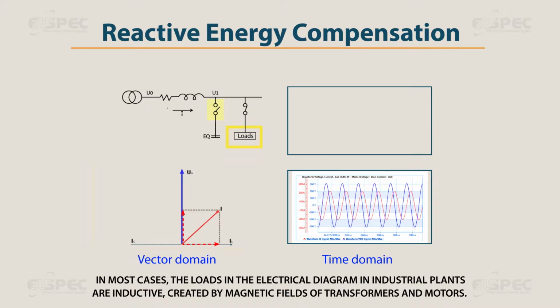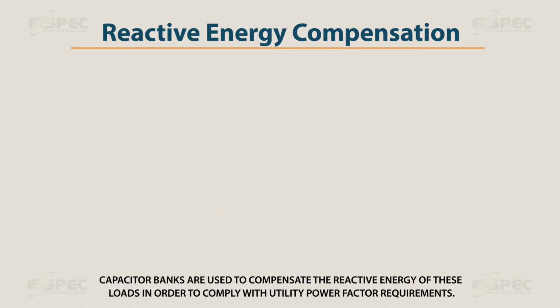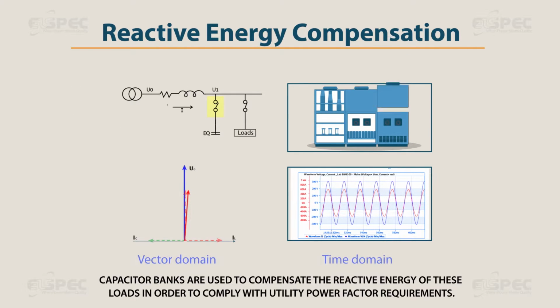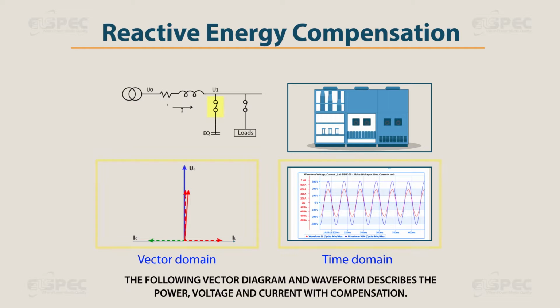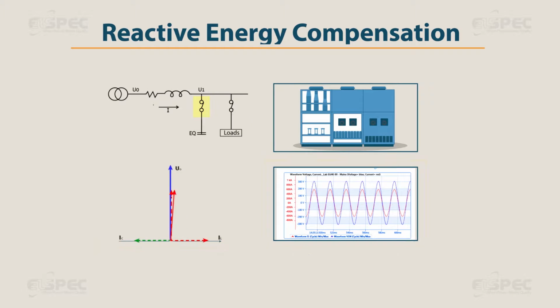In most cases, the loads in the electrical diagram in industrial plants are inductive, created by magnetic fields of transformers and motors. Capacitor banks are used to compensate the reactive energy of these loads in order to comply with utilities' power factor requirements. The following vector diagram and waveform describes the power, voltage, and current with compensation.